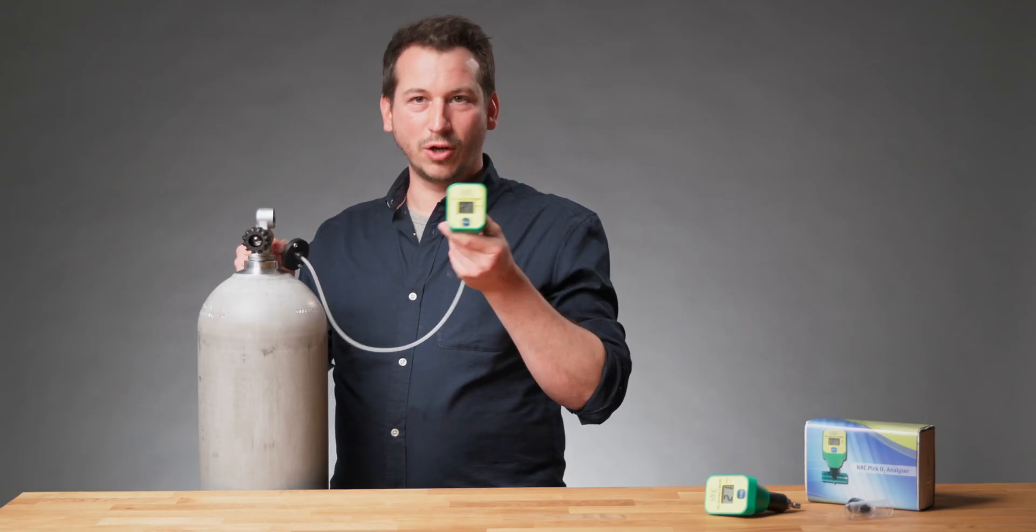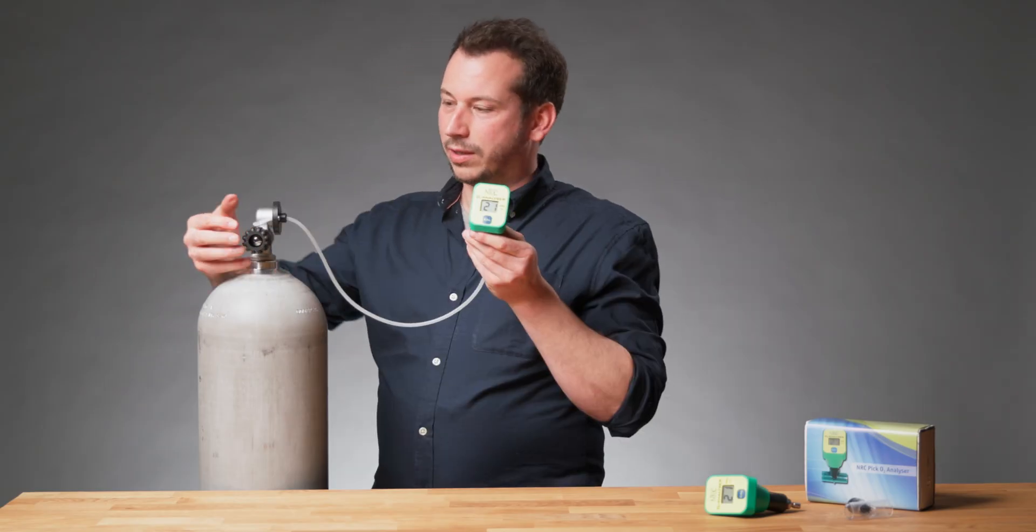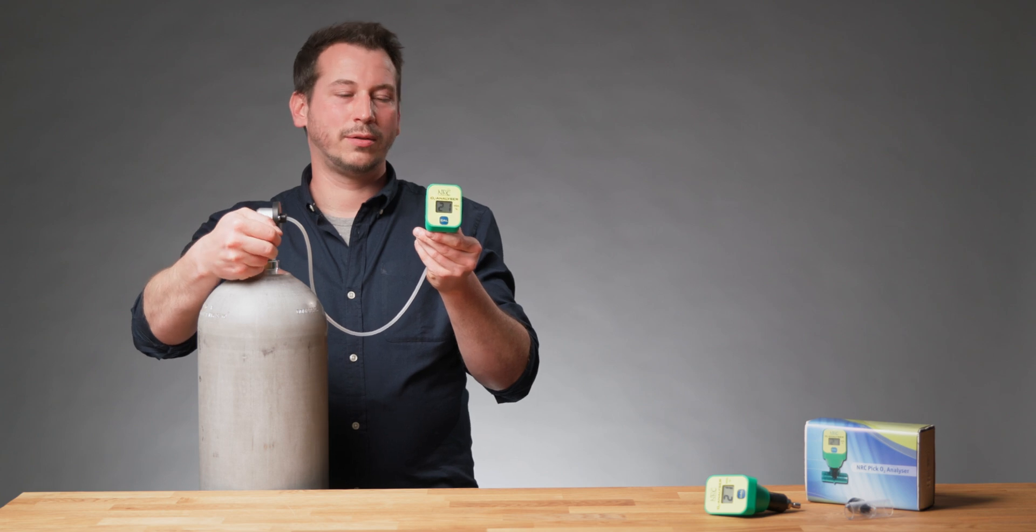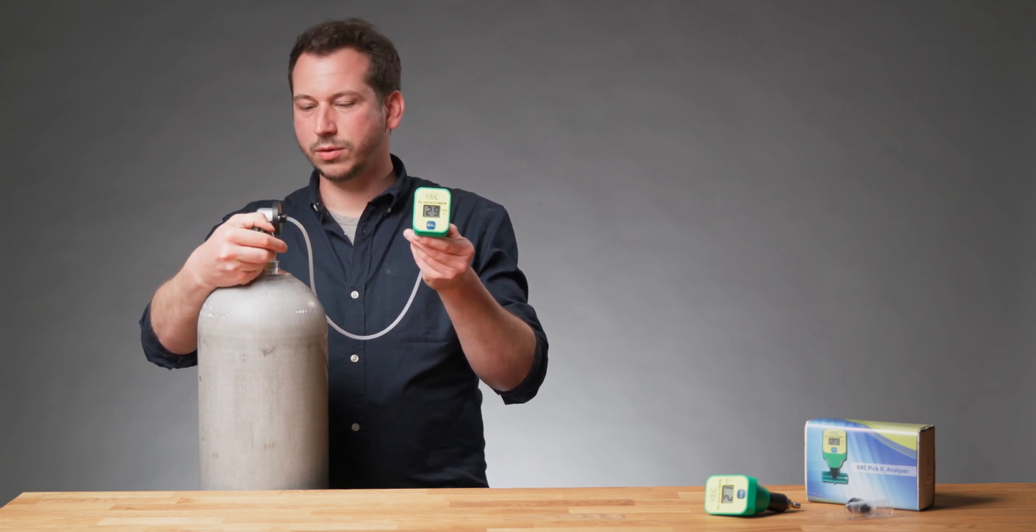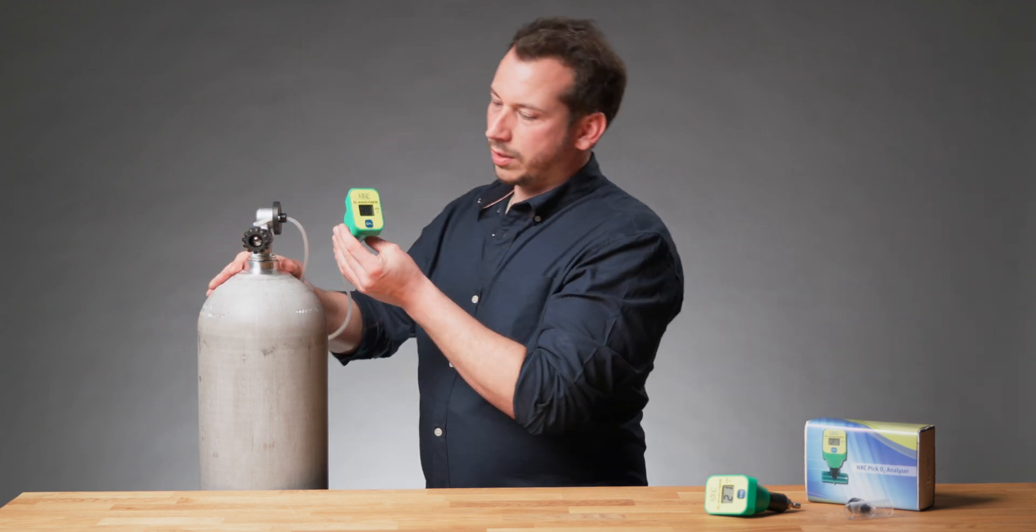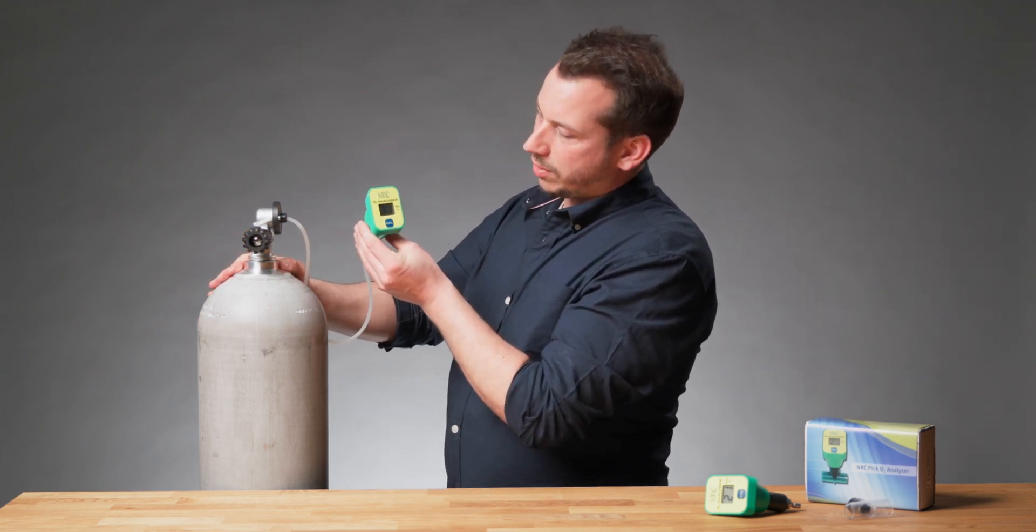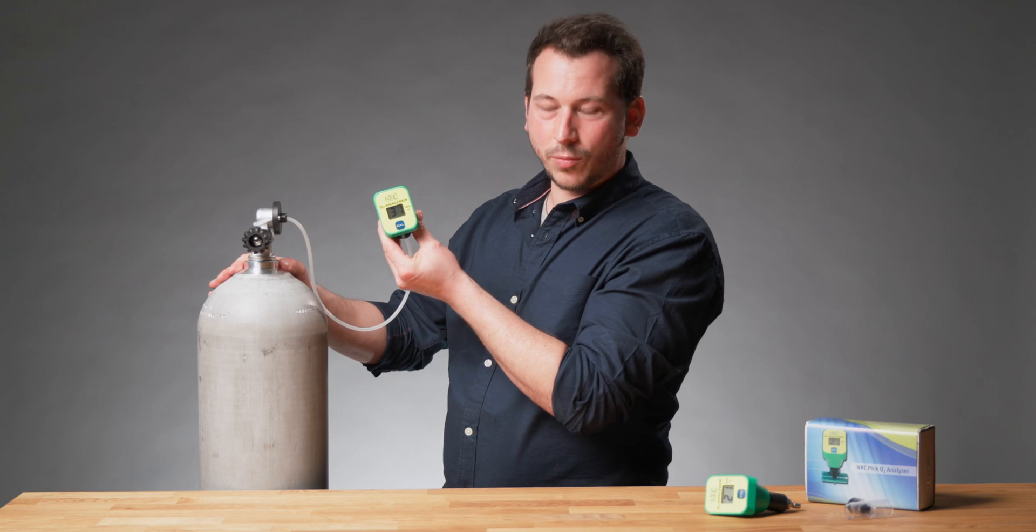We don't need to calibrate it now because we just did it before. And now we just gently open the valve until we hear a slow flow of gas coming out. After we see directly, the percentage is going up on the analyzer.